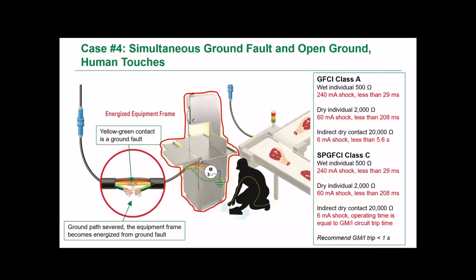Now, there are devices on the market that can de-energize the circuit based on the response from the ground monitoring in under 500 milliseconds. And certainly, due to the safety benefits of a fast-acting GMI circuit, we really would recommend a device with that trip level under 1 second. So we can see here is where it comes into play.